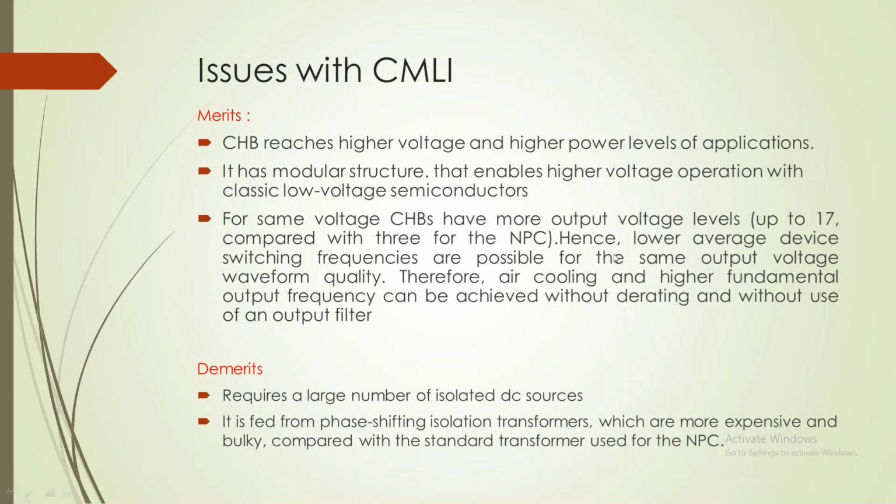Right. These are all the practical problems. If you do simulation of NPC in MATLAB, that shouldn't be a problem. But when you go for practical, NPC cannot be employed beyond 3 levels unless you solve the capacitor balancing problem. But with cascaded H-bridge, I can go for 17 levels or higher. So the voltage rating of each switch will come down, and I can go for employing a lower voltage rating switch. So that is a major advantage of cascaded H-bridge.